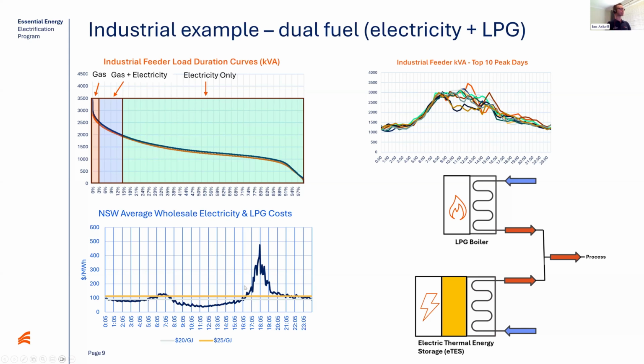Explaining this concept back to that load duration curve - typically for only about 3% time duration in the year, so say 10 days accumulated, the network is under stress. During that time period, we're looking at the economics of running that LPG boiler. Then during lower demand times, on a dynamic basis as I mentioned, we'd be signaling in real time the spare capacity in the network. You could look at a blend arrangement to meet your on-site daily heat needs, or where there's significant spare dynamic capacity in the network, run purely on electricity.